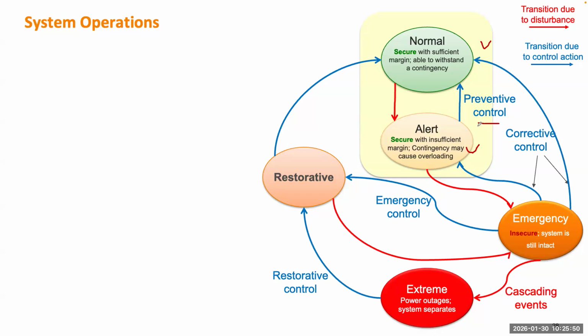But if you want to take the risk, you can do nothing, right? You can just stay there and wait. Maybe the system will increase the margin on its own. For instance, if the load declines. Right now you're operating during the peak hours, the load is very high, like 4 p.m. And based on your calculations, if this line is open, the neighboring area will have lower voltage and other lines will be overloaded. But you just cross your fingers and think maybe next hour the load declines and my system will be fine. So you don't have to do anything. But if you want to do something, that's called preventive control. Both the normal state and the alert state are considered normal operating conditions.